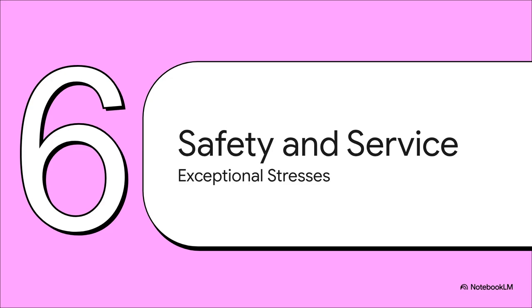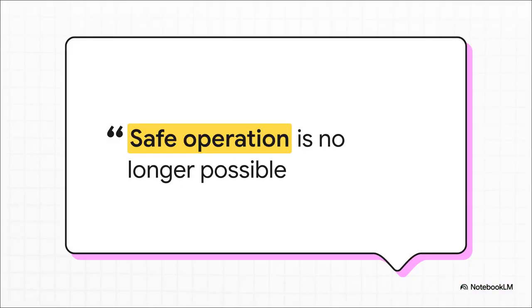Section 6. Safety and Service Exceptional Stresses. We've talked a lot about the limits of sound, but we also really have to acknowledge the physical limits of the machine itself. The safety guide is wonderfully, starkly blunt about this. If you even suspect safe operation of your DM5E is no longer possible, you must immediately disconnect the instrument, secure it against unintentional use, and take out the batteries. You don't tinker with it, you don't just cross your fingers and hope it gets better, you shut it down.